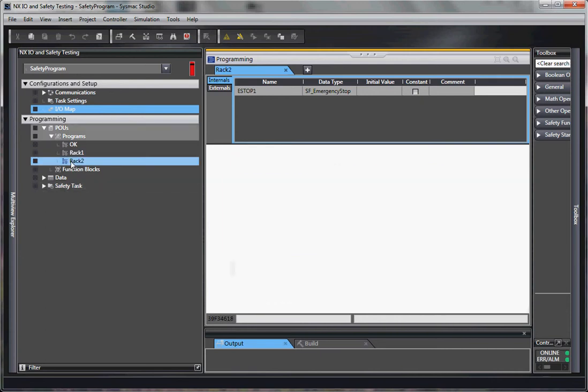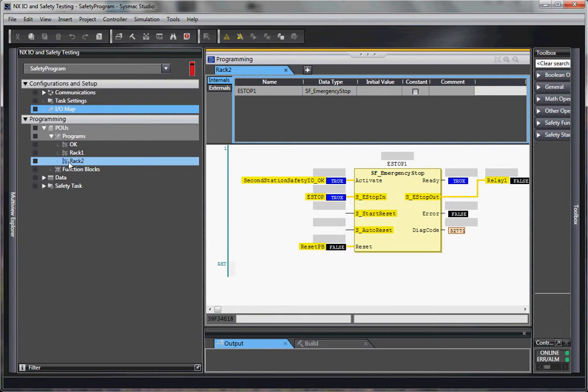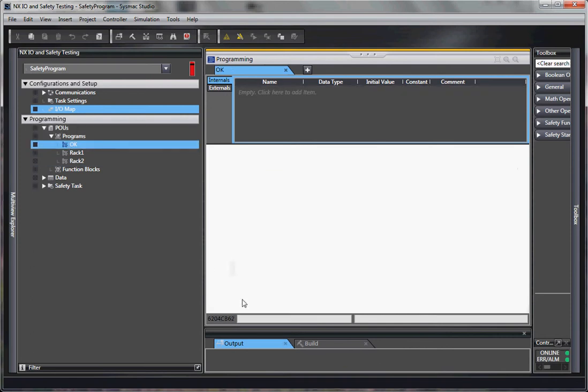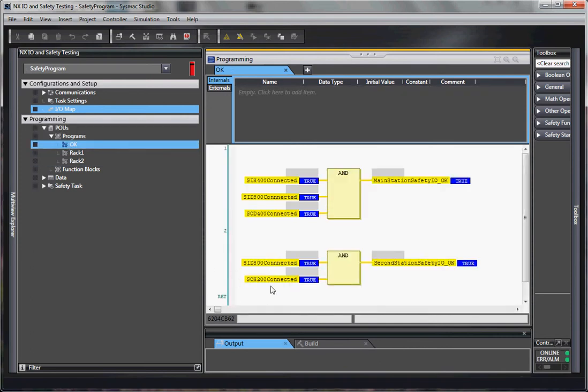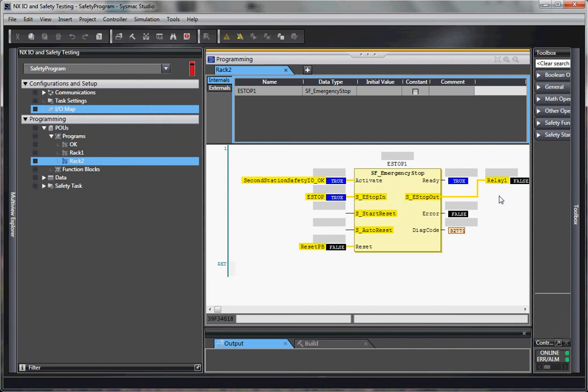Here's the trick. In rack 2, and this is the rack that I want to be able to disable, the node. This bit will turn off. If this card is disabled, this bit will turn off. When this bit turns off, it deactivates this function block. When I deactivate this function block, it can no longer check to see if its I.O. existed. In this case, relay 1 is the one that's going to stop existing when node 2 is disabled. Therefore, it does not cause an error.